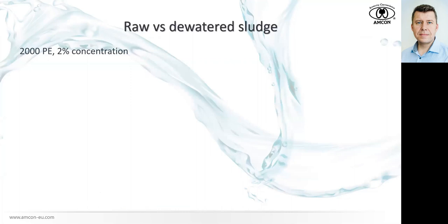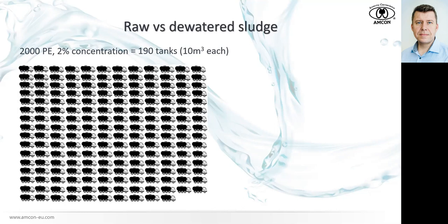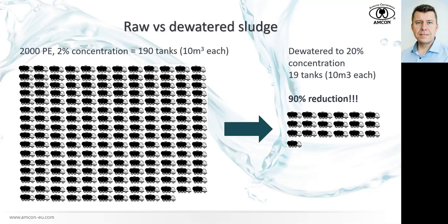Raw versus dewatered sludge. 2,000 population equivalents — a small village or really small town — at 2% concentration will produce something around 200 tanker trucks, 10 cubic meters each. If we manage to dewater the sludge and increase concentration from 2% to 20%, the reduction is around 90%: instead of 190 trucks, we have 19. Of course, 20% sludge is not liquid anymore — it's already in a solid state — so this is just for easy comparison.